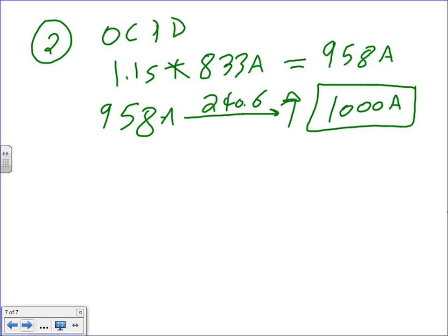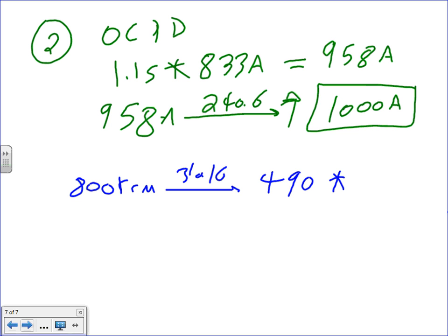So we had an 800 kcm. Holly, from 310.16, what was the rating? 490. Multiply this by 2, guys, because we have 2 of them. 980. 980 amps.